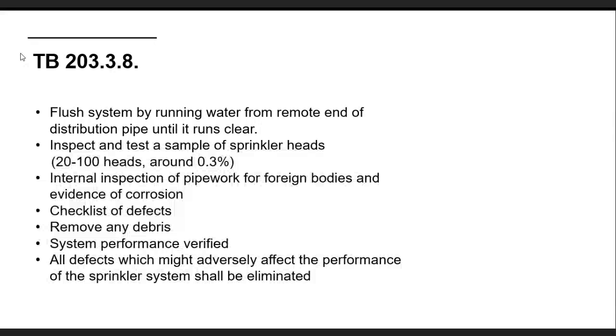Remove any debris - that's pretty obvious. We're going to have a thorough flush through, and probably take the pipework apart in key places. Your sprinkler or service contractor will be able to advise you on that. If you've got a large pipe which turns a corner and then drops in size to a smaller diameter, that's a good place where we're probably going to catch a lot of debris. So it might be a good idea to remove a few joints around that area and see what debris you've got in there.